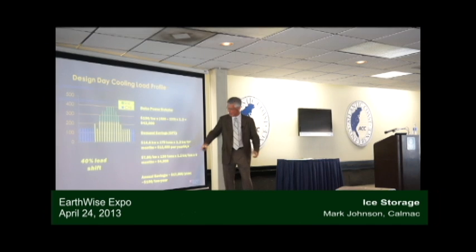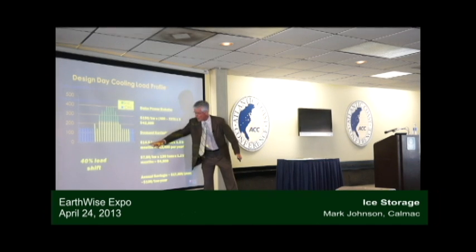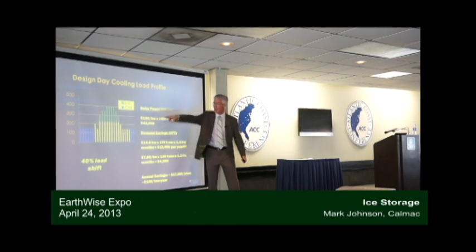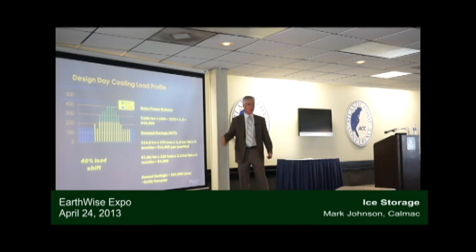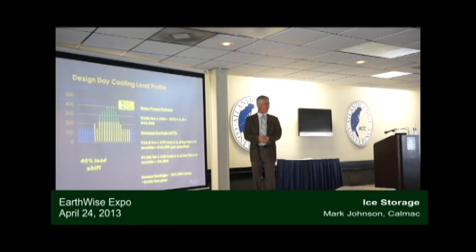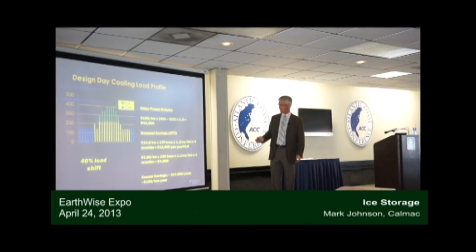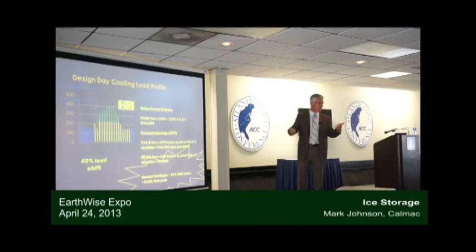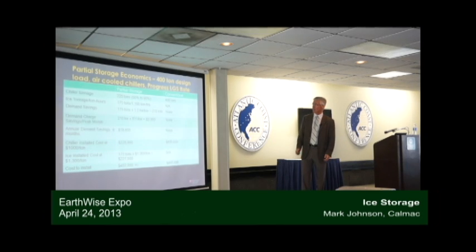So what's that savings driven by? It's driven by the demand charge, and it's driven by the load shift. So you've got to design with those two things in mind. That's a lot of money. If we could shift 700 tons of load, 700 tons times about 100, you're looking at $70,000 a year in demand savings.